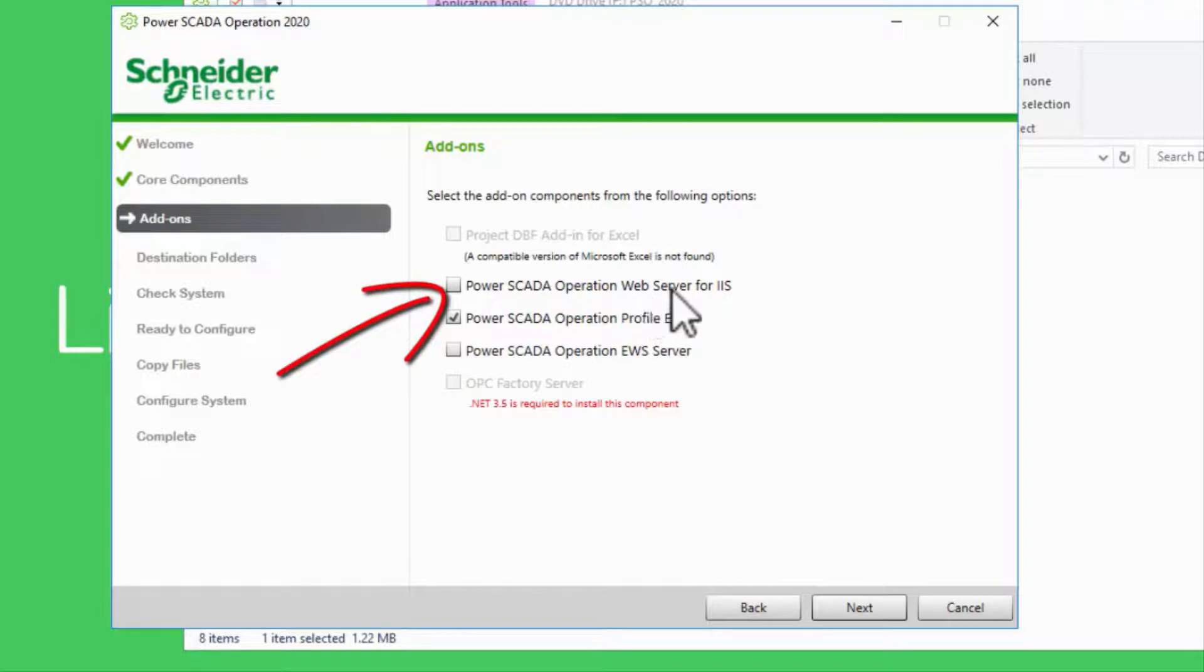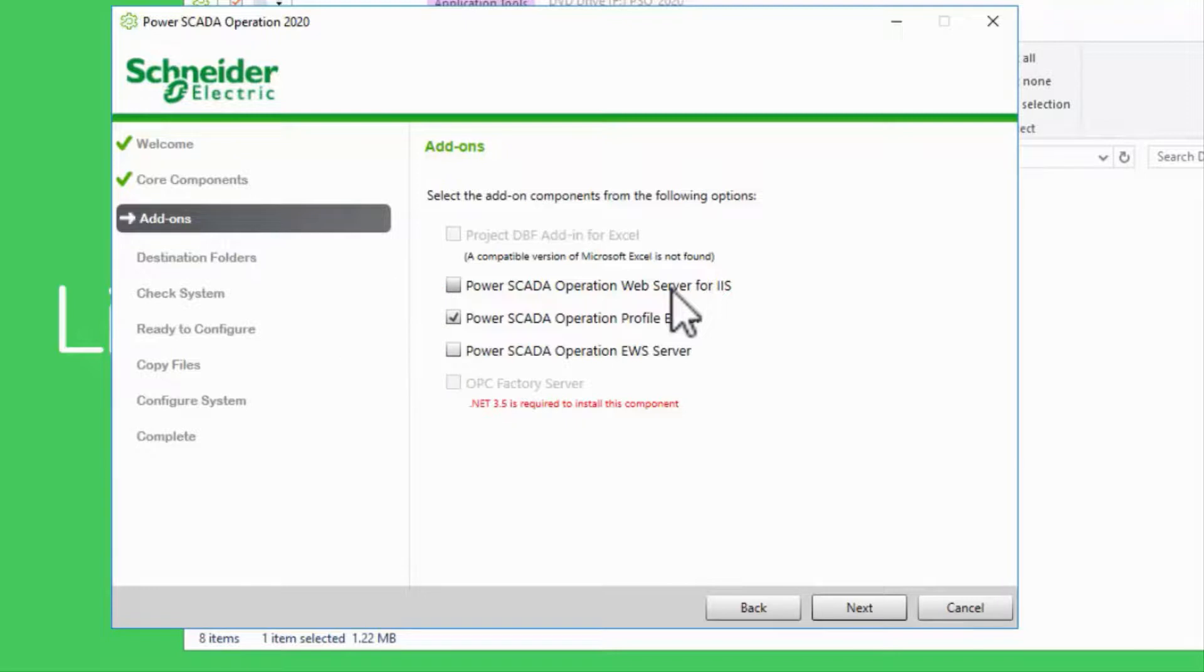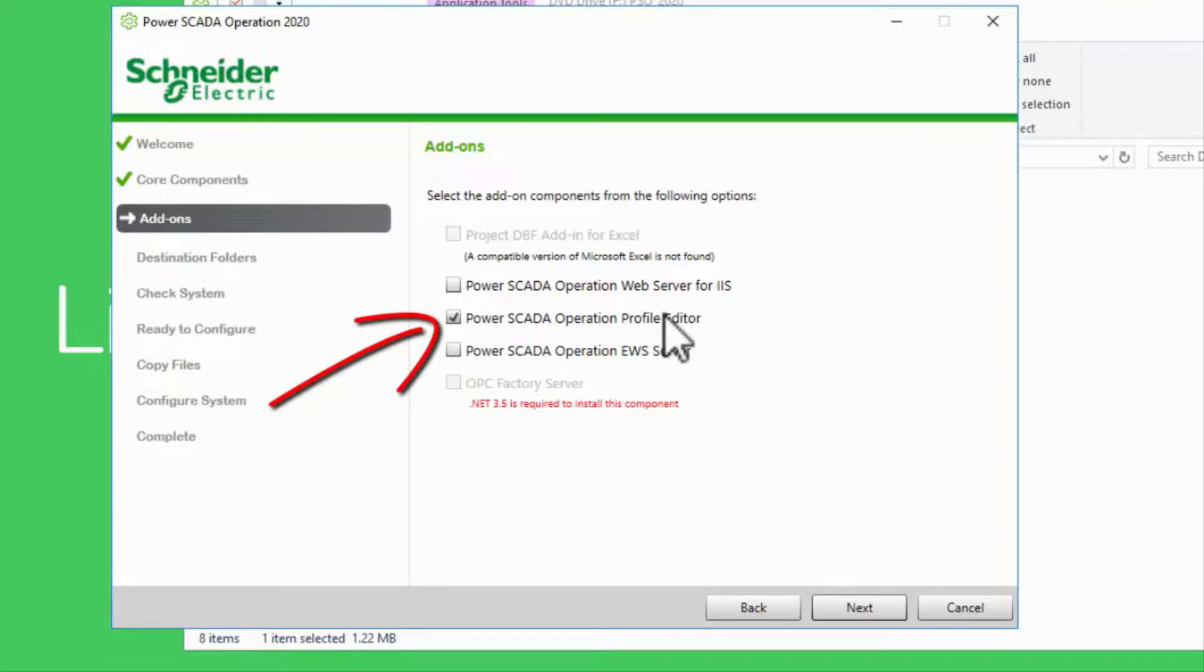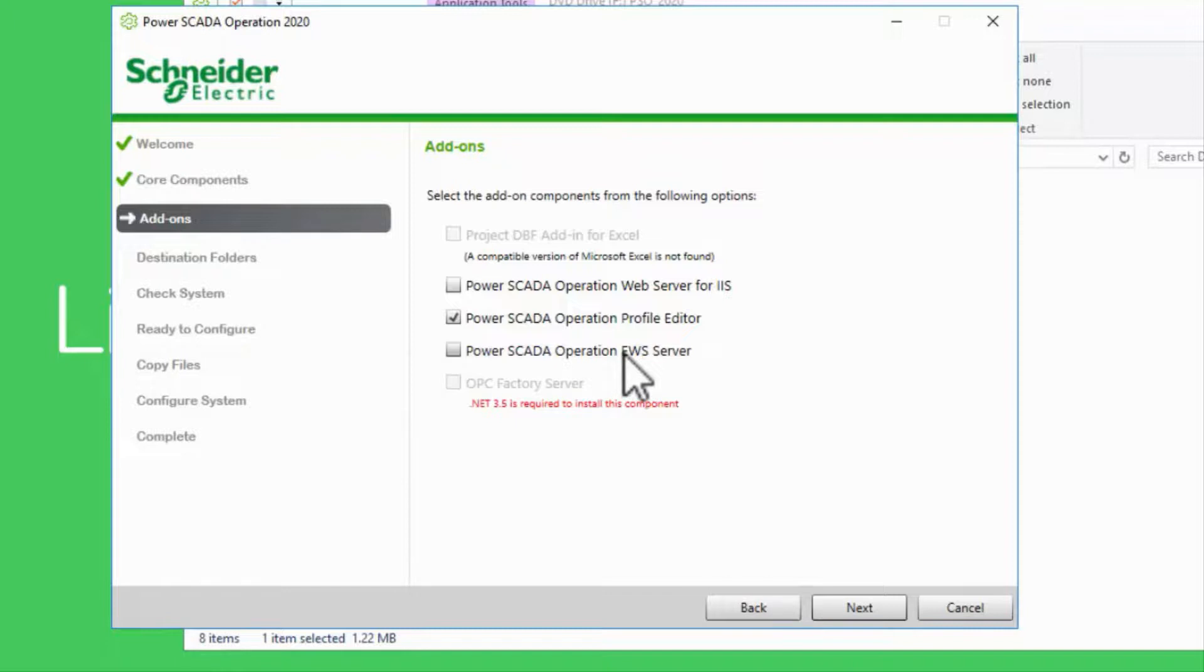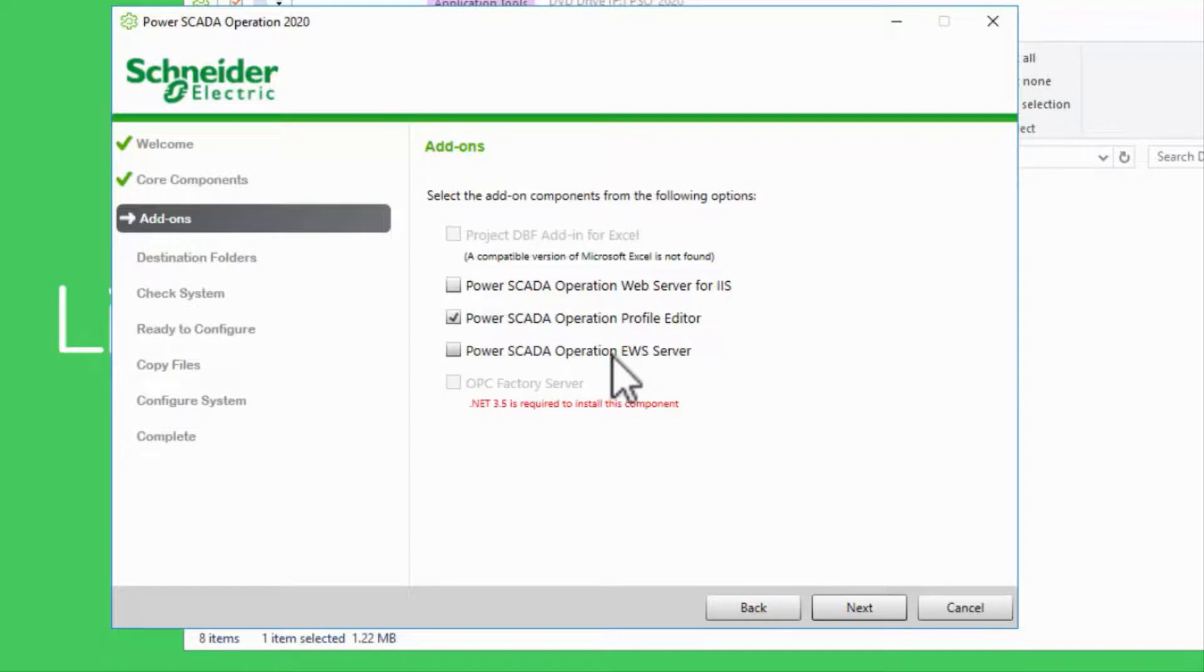The web server for IIS is the legacy web server and not necessary for the HTML5 web client. The profile editor is a critical component in adding devices to a project. The EWS server is used to provide data to other Schneider Electric software packages, and I also have a checkbox to automatically install the OPC factory server mentioned earlier. In short, the default options here are generally correct unless you know otherwise.